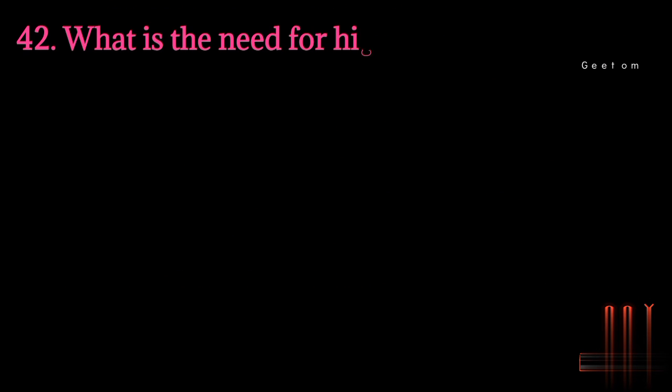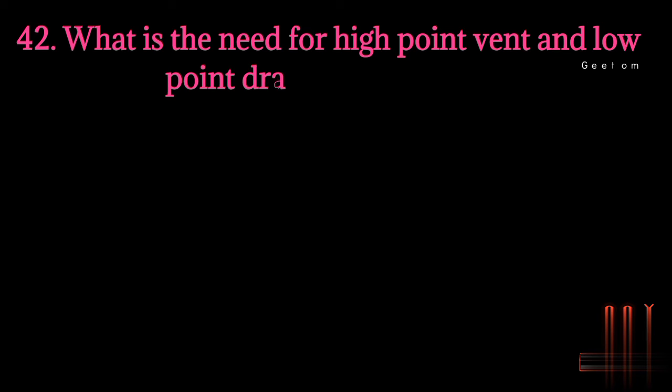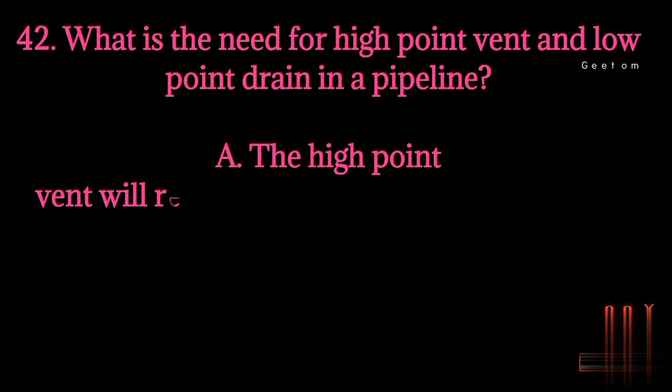Question 42: What is the need for high point vent and low point drain in a pipeline? Answer: The high point vent will remove the air during the hydro test and the low point drain would drain the water after the hydro test.